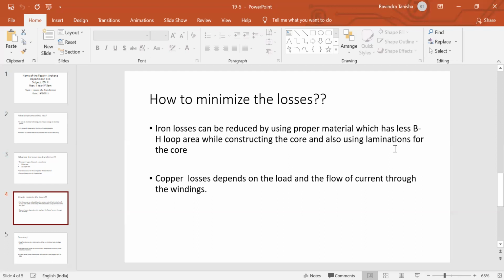Eddy current loss can be reduced by using laminations for the core part. So iron loss, which is the combination of both hysteresis and eddy current losses, can be minimized by choosing a proper material, like sheet steel, cast iron, cast steel, CRGO material. All these materials have very little BH loop area. So if you use this material for the construction of the core, automatically the hysteresis loss is reduced. If you use thin laminations instead of a bulk core, then automatically you can reduce your eddy current loss, which is a part of iron loss. This is how you can minimize the iron loss, the hysteresis and eddy current losses.